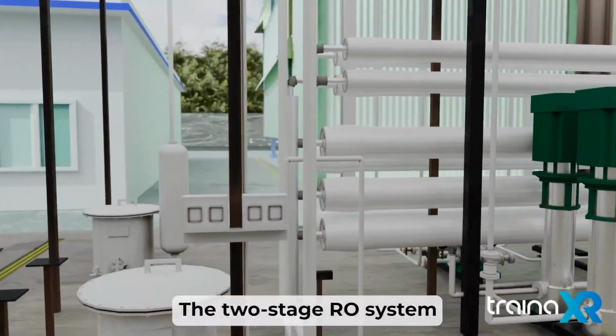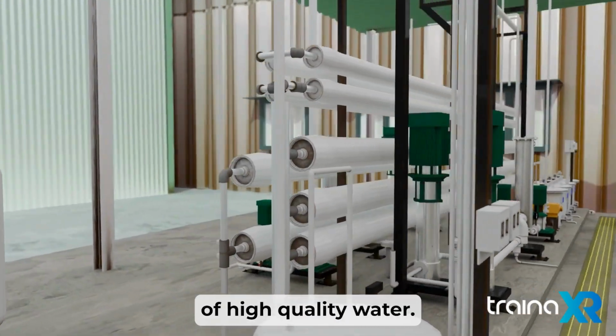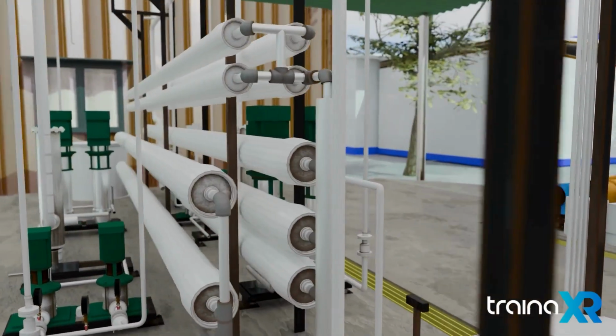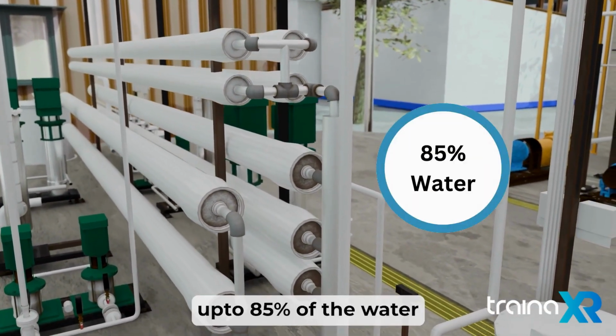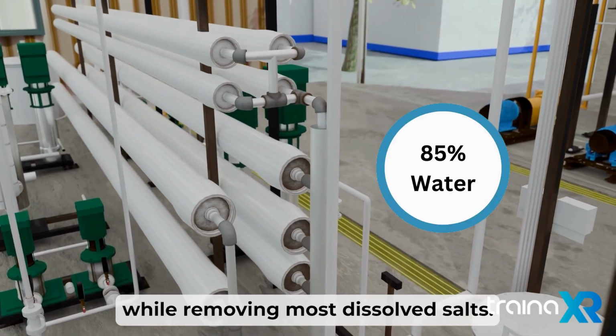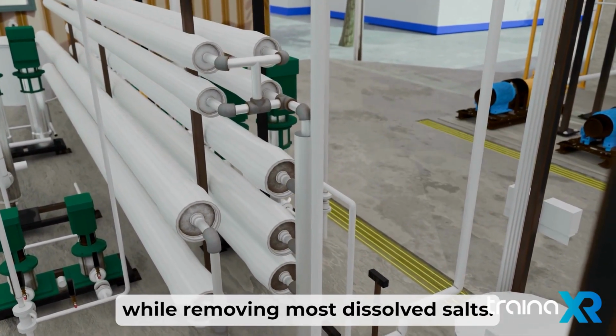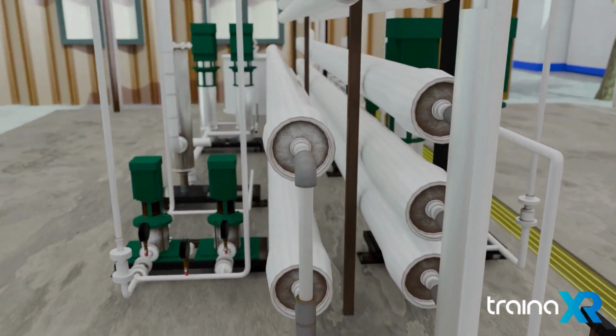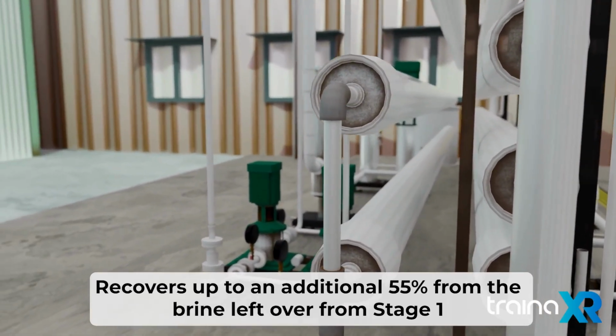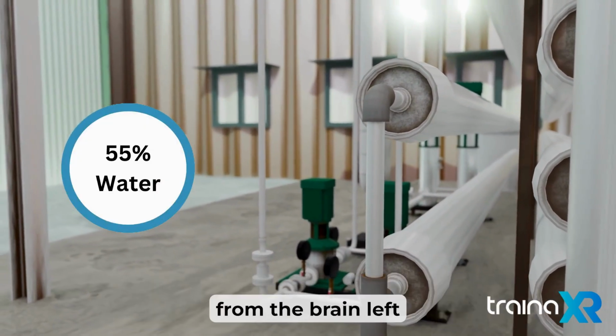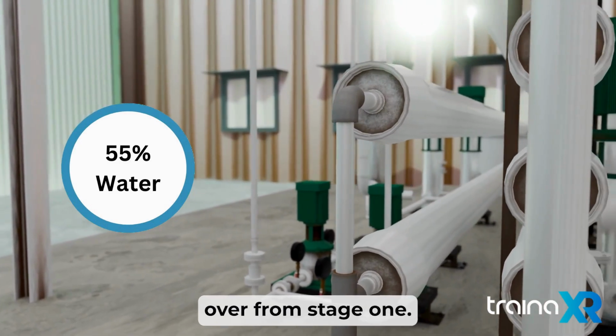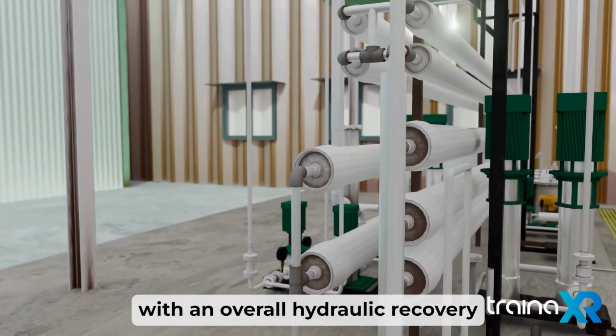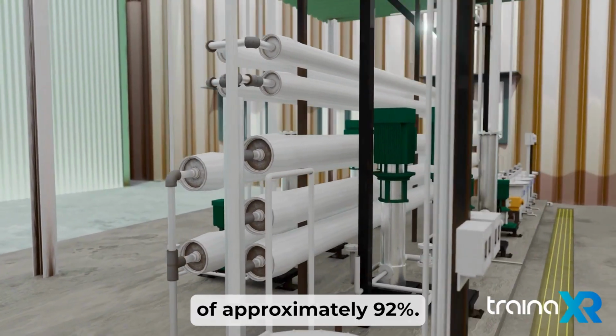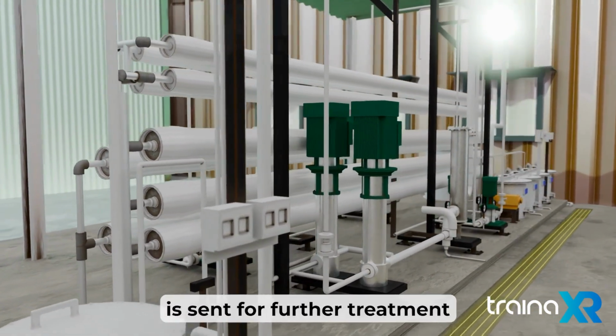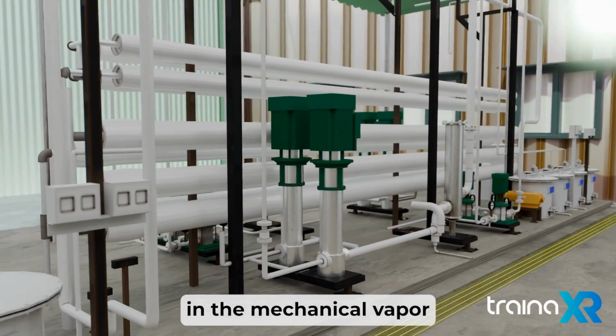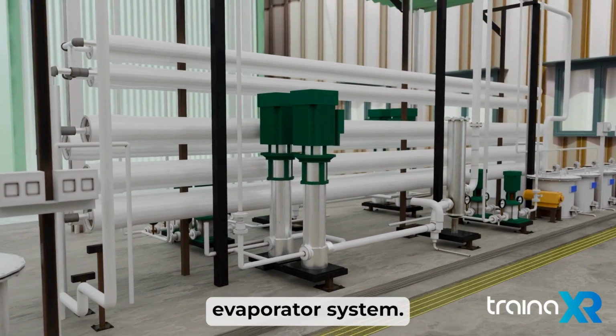The two-stage RO system ensures efficient recovery of high-quality water. Stage 1 recovers up to 85% of the water while removing most dissolved salts. Stage 2 recovers up to an additional 55% from the brine left over from Stage 1. With an overall hydraulic recovery of approximately 92%, only a small volume of brine is sent for further treatment in the mechanical vapor compression-based evaporator system.